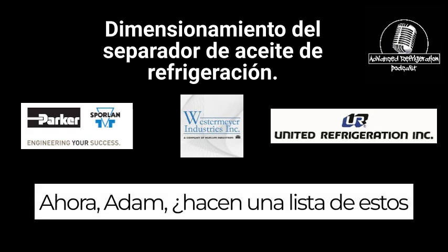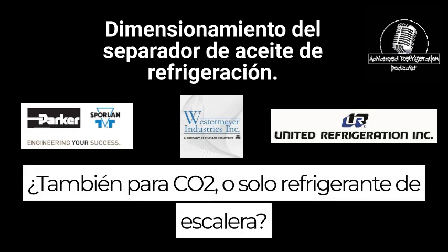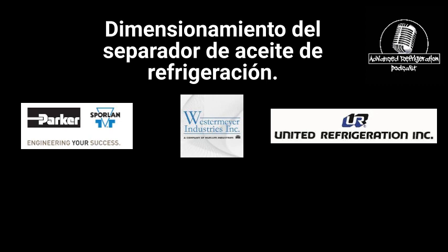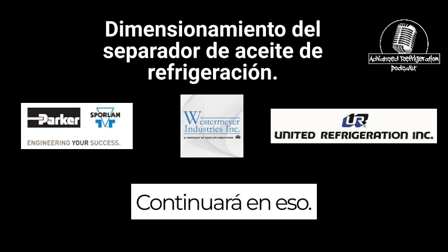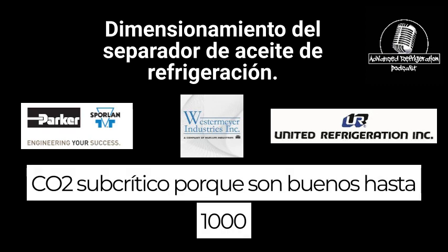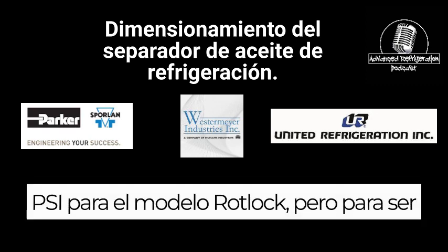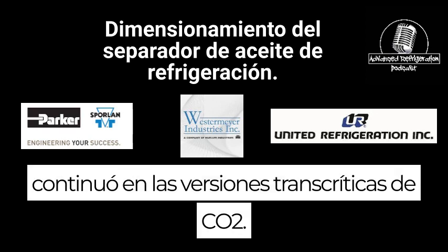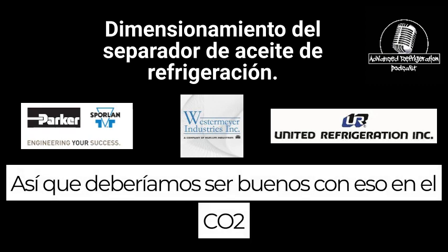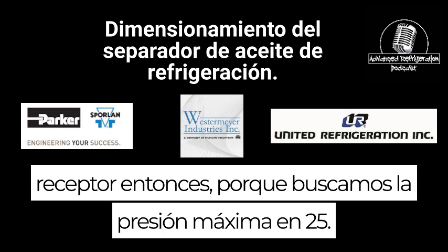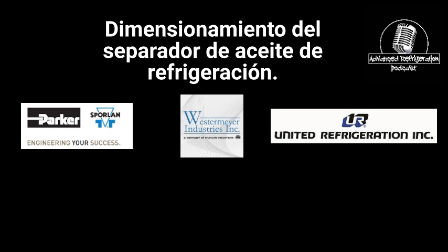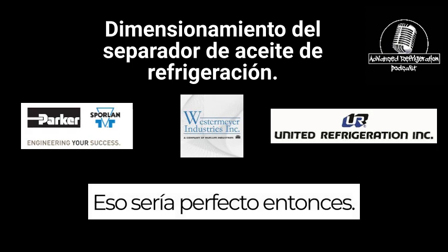Now, Adam, do you guys list these for CO2 also, or just the standard refrigerant? To be continued on that, Kevin, with CO2. You can use these for subcritical CO2 because they're good up to 1,000 psi for the Rotolock model, but more to come on the CO2 transcritical versions. So we should be good on the CO2 receiver then, because we're looking at a max pressure of 525. That would be perfect then.